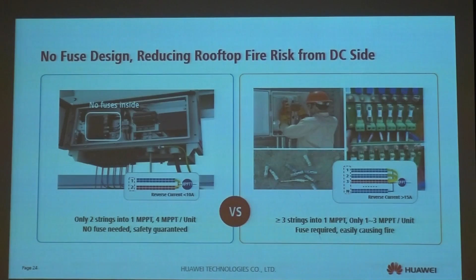But for others, they have fewer MPPTs, so each MPPT collects more strings. In this case, if a short circuit happens, the reverse current could be more than 10 or even 15 amperes, so they have to use fuses for protection. But fuses are vulnerable parts — they need regular maintenance, inspection, and replacement. Over a 25-year lifetime, this will cost a lot of labor and money. So in this case, we help you reduce the CAPEX and OPEX.